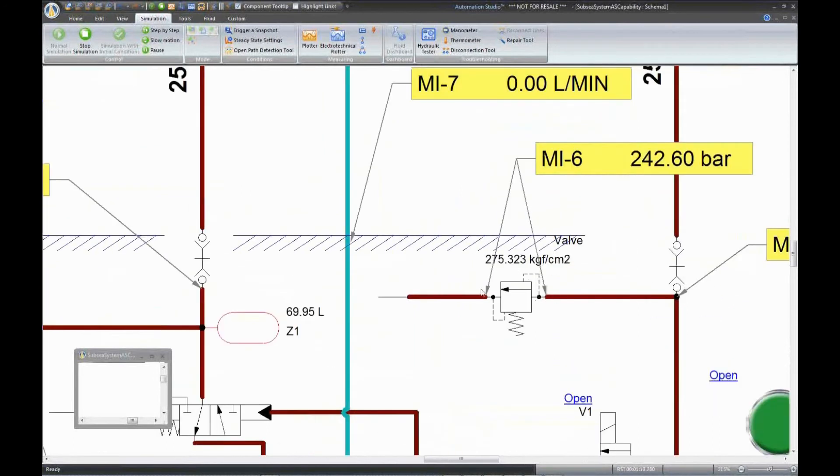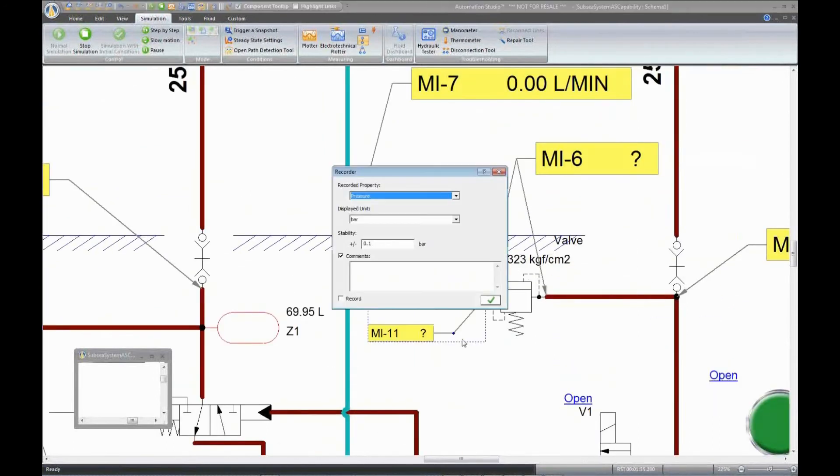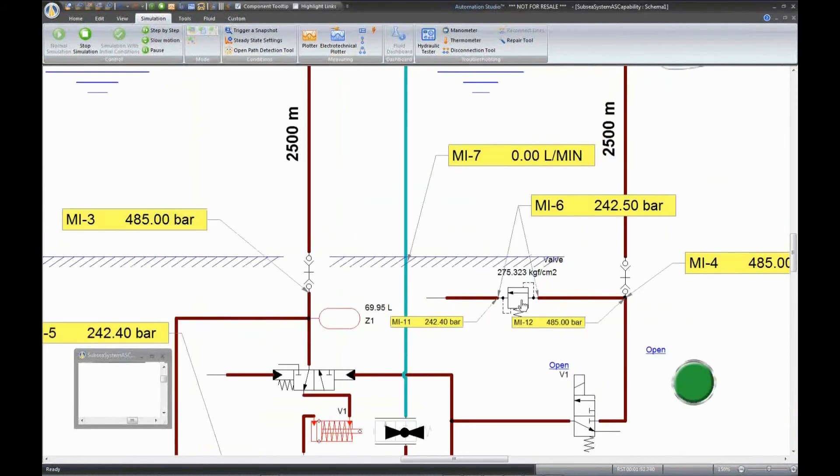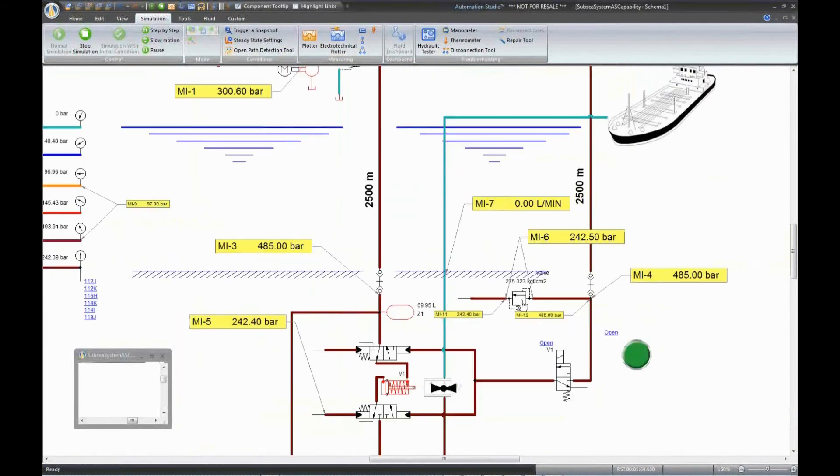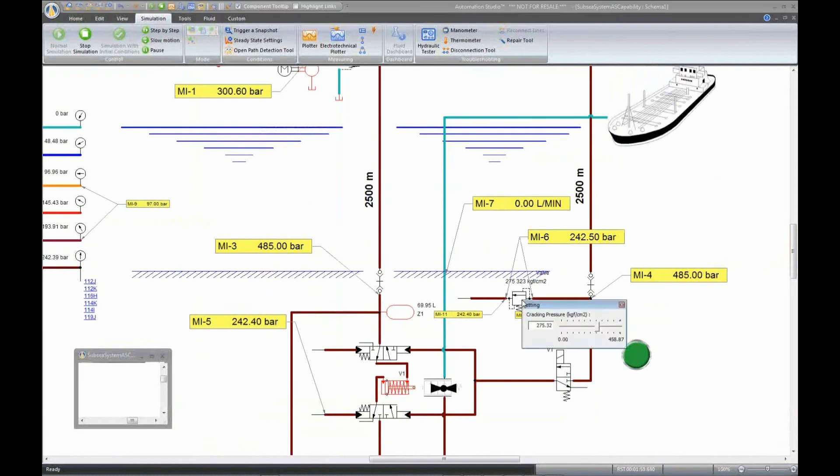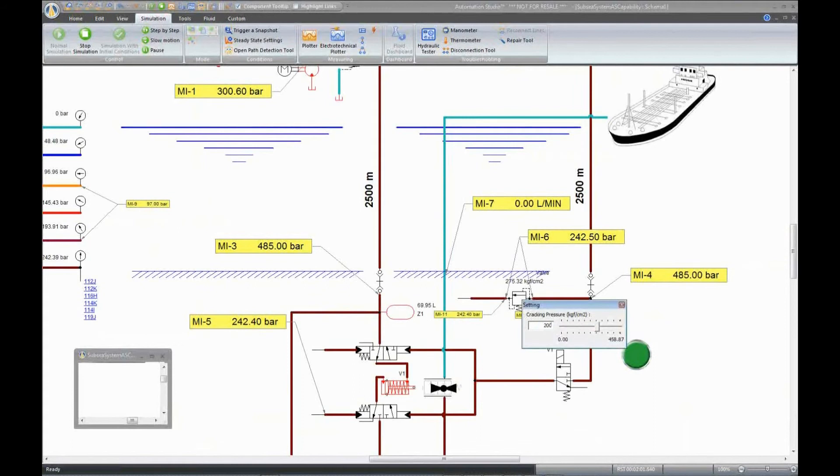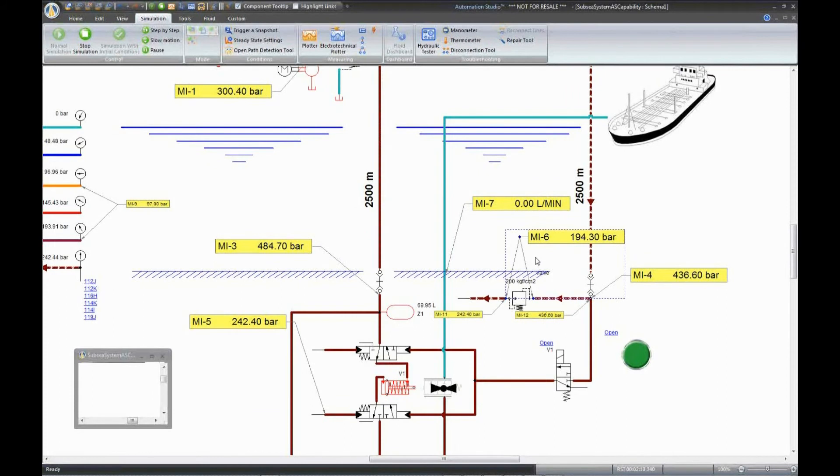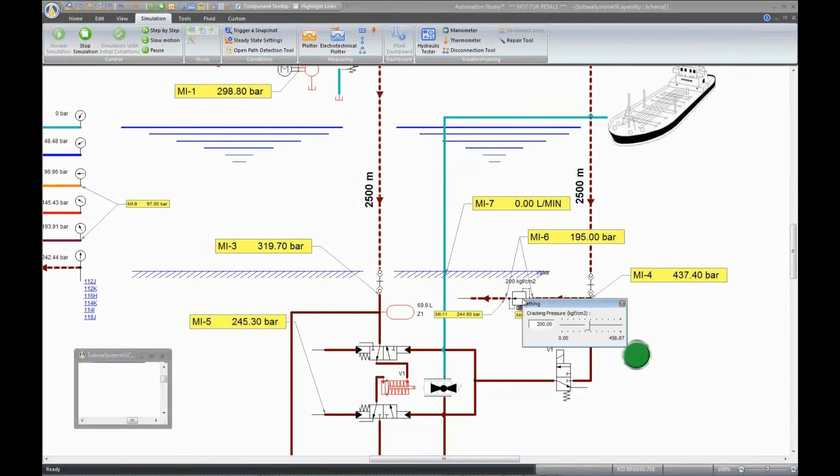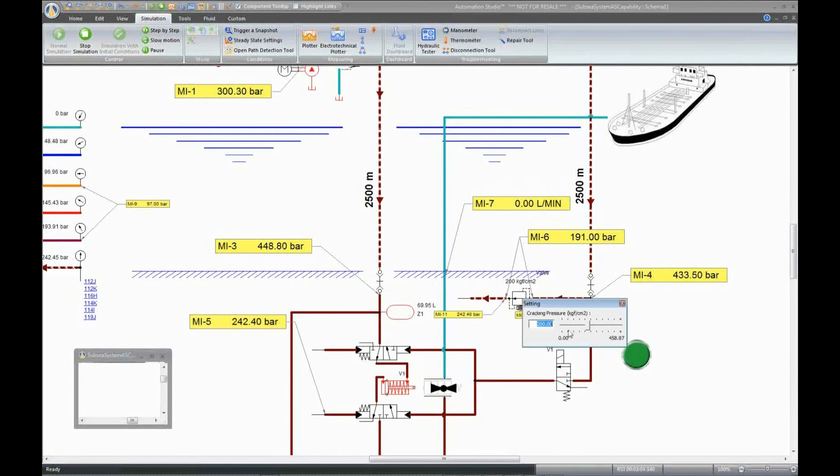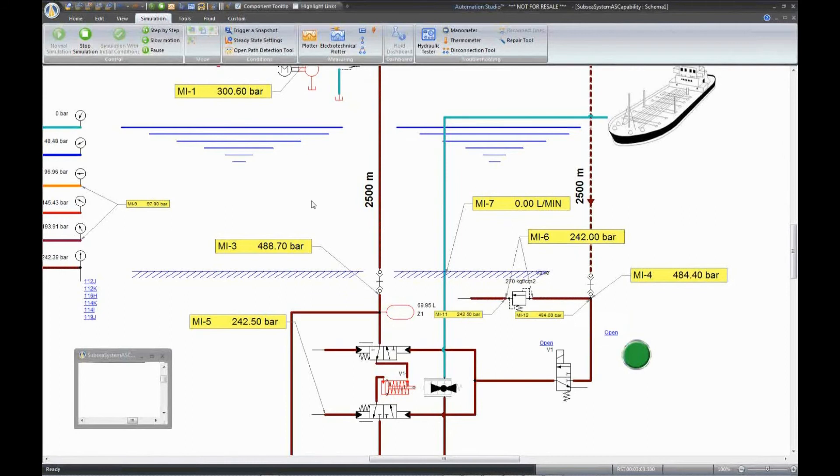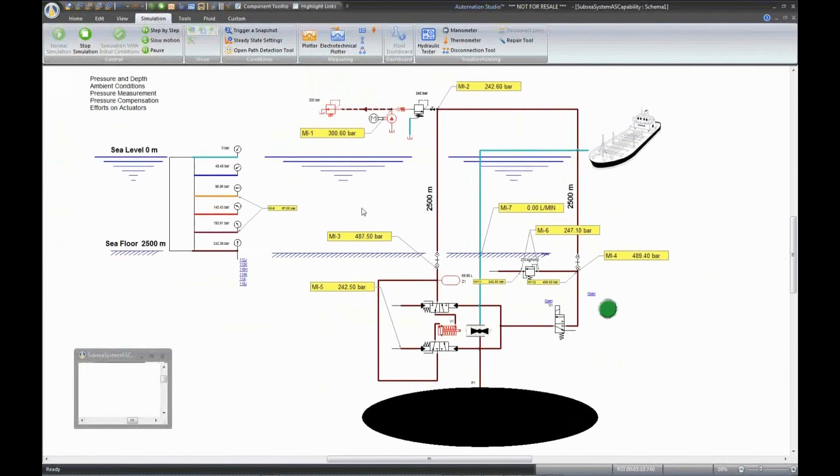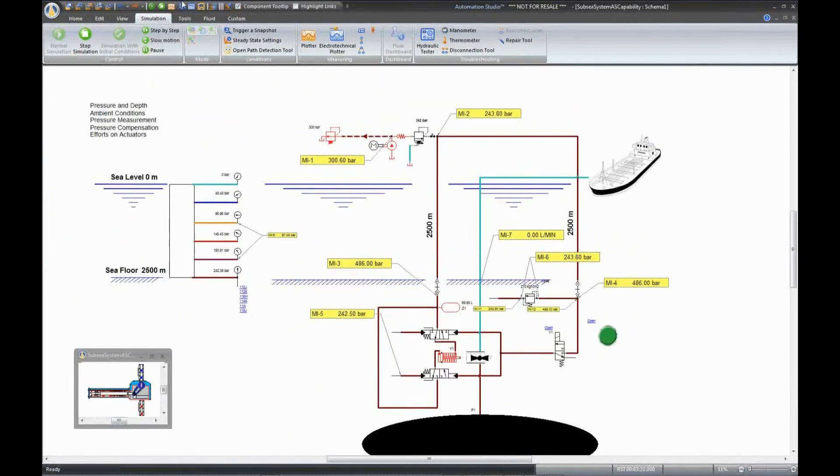Since subsea systems are located at different depths, compensated sequence valves are used. This valve is affected by the exhaust pressure. For example, we have a differential pressure of 200 bar, and this valve opens at this pressure. The fact that the valve remains open at 194 bar is due to its deadband.